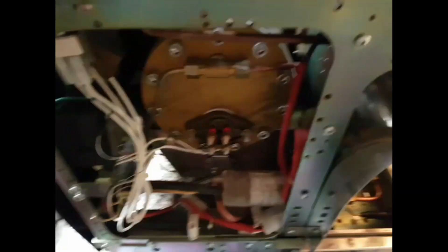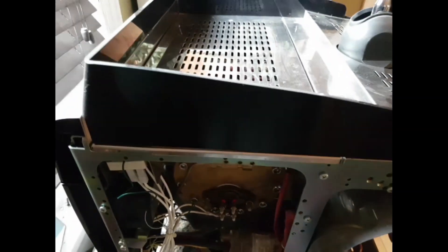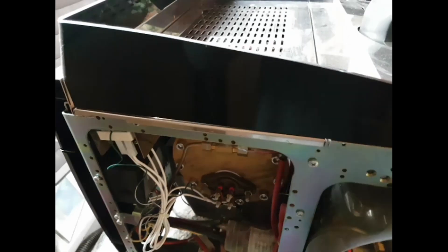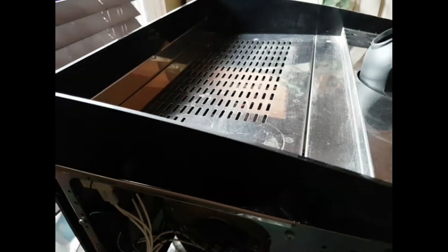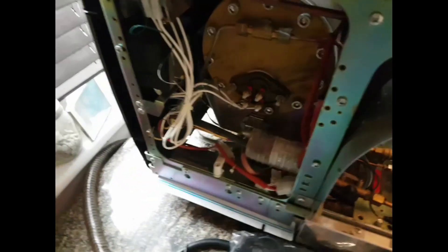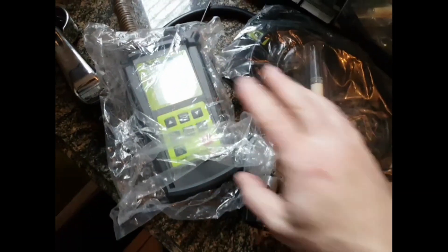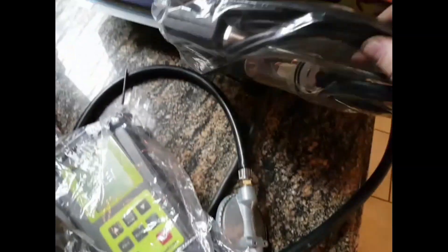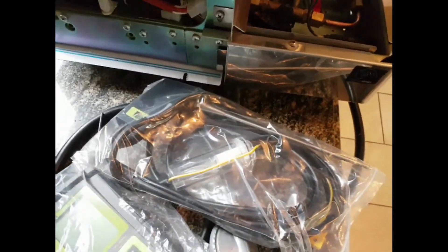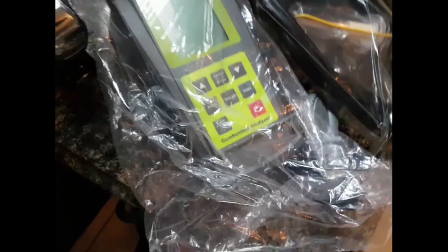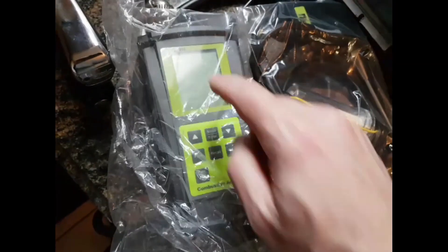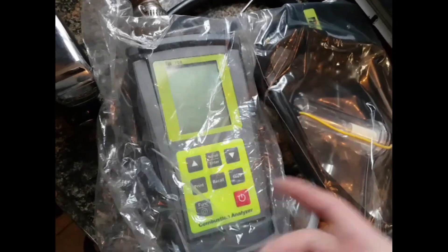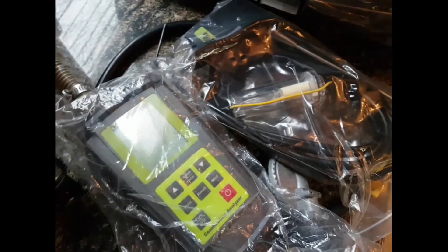So at least once a year, I recommend that someone take an air-free CO reading of the gas coming out of the top, the exhaust gases coming out. And for that, I use this combustion analyzer. So here is the wand or sniffer. You basically just place this right on top of the grate. Turn this on and it will aspirate some of the exhaust gas into the machine and tell you what your CO reading is. That's basically how it's done.